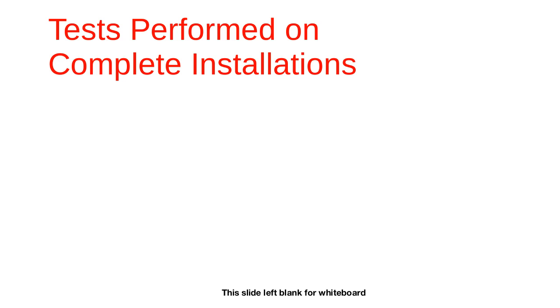I've said number one, visual inspection ensures that the equipment that has been used complies with the product standard. Number two is that equipment is correctly selected and erected. And number three, equipment is not damaged. So those are the three major purposes of visual inspection under tests and inspection as per the IEE regulations and standard.